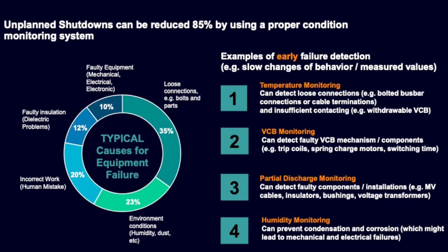Vacuum circuit breaker operation mechanism monitoring can detect faulty VCB mechanism and components. Partial discharge monitoring can detect gradual degradation of insulating properties for support insulators and bushings.